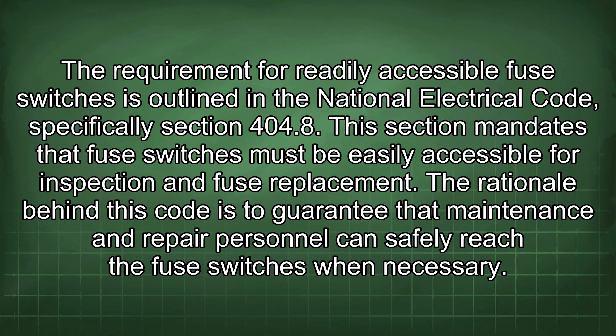The requirement for readily accessible fuse switches is outlined in the National Electrical Code, specifically Section 404.8. This section mandates that fuse switches must be easily accessible for inspection and fuse replacement. The rationale behind this code is to guarantee that maintenance and repair personnel can safely reach the fuse switches when necessary. When fuse switches are installed at elevated positions, such as 15 feet above the working surface, hook sticks or ropes become essential tools. These tools provide a safe and convenient way to reach the fuse switches without the need for ladders or other potentially hazardous climbing equipment.